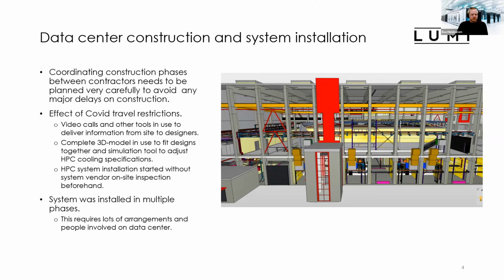Actually, it was pretty good that we had a complete 3D model in use to fit designs together. And we had a simulation tool to adjust the HPC cooling specifications during the construction, adjust the final components, and do some pre-tuning for the control system before the actual system tests. Having these kinds of tools in use reduced the time for system testing quite a lot. With the 3D model we avoided a lot of issues on the construction site when planning pipelines and cable routes in the very tight space underneath the data center raised floor.